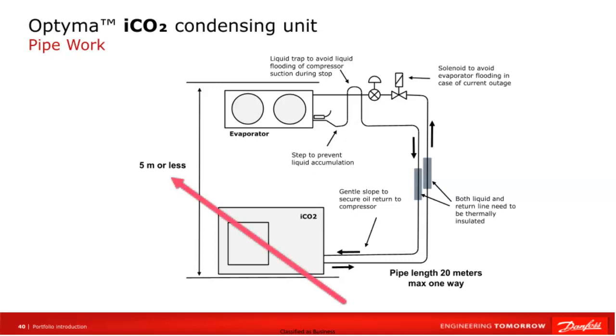Elevation up to 5 meters, maximum pipeline length of 20 meters. Both the suction and liquid pipelines should be properly insulated. It is recommended to use a solenoid valve. It is important to prepare a liquid trap. A step in the pipeline may be necessary to prevent liquid from accumulating at the valve. By taking care of this aspect, we will ensure the proper functioning of our refrigeration installation, even if the evaporator is installed at the top and the condensing unit at the bottom.